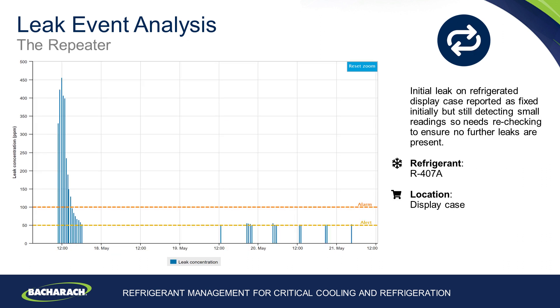Here is the final leak event example — the repeater. In these examples a leak has been found and rectified, but a few days later PPMs are detected again from the same asset, indicating the original leak wasn't fixed correctly. Having the on-site leak detection system and smart monitoring helped pick this up. A return to site by the refrigeration engineer to correctly rectify the fault mitigated any further refrigerant loss, and the permanently monitoring system helped prevent further losses from the system.